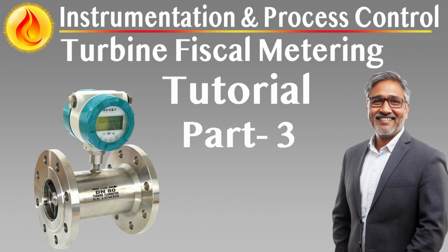Construction must follow best practice geometries such as tube bundles, vane plates, or perforated flow conditioners with minimal additional pressure loss. The design must be fabricated from corrosion-resistant materials, ideally stainless steel, and matched to the internal diameter of the meter run to maintain laminar alignment. Welds and internal surfaces must be free of burrs, protrusions, or roughness that could disrupt the flow.